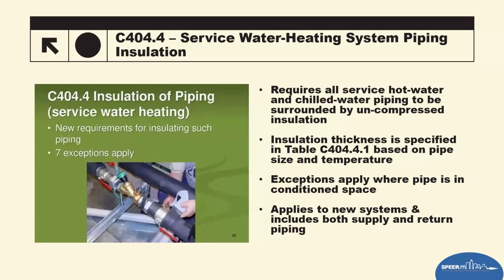Still staying in line with that for service water heating, C404.4 mandates that service water heating piping, both hot and chilled loops, must be insulated with specific minimum insulation to minimize thermal losses through those pipes. This ensures that the piping between the heater and the fixtures or circulation loops is not neglected, and that the efficiency is maintained. The code also includes a dedicated table, C404.4.1, for insulation thickness and clarifies piping inside conditioned space or buried in different settings.